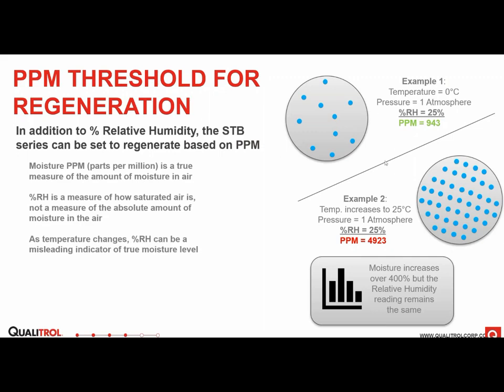So these diagrams kind of speak a little bit louder than words here. Consider both of these at 25% relative humidity. They're at the same pressure, but at different temperatures. As you can see, at 25C there's a lot more ppm of moisture, even though both of these readings are 25% RH. Where this becomes an issue is if you have 25C in the afternoon and then drop to a really low temperature at night, there's a lot more moisture being inhaled into your transformer. But if you were using ppm, you could more accurately track the saturation of the silica and get on a better regeneration cycle.